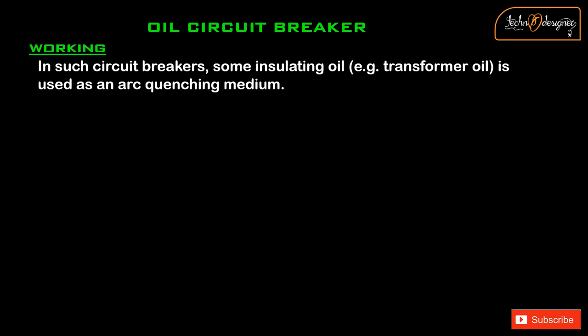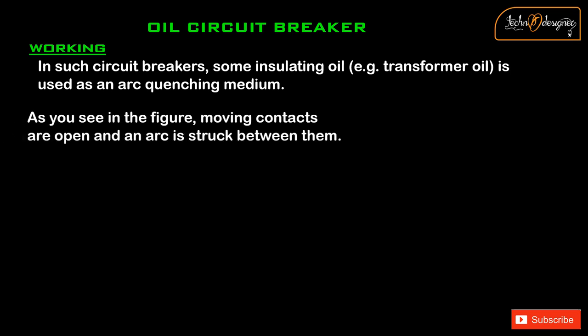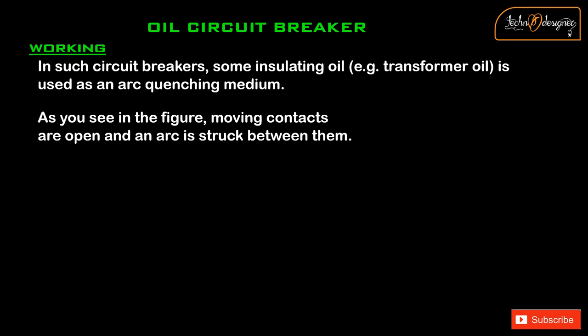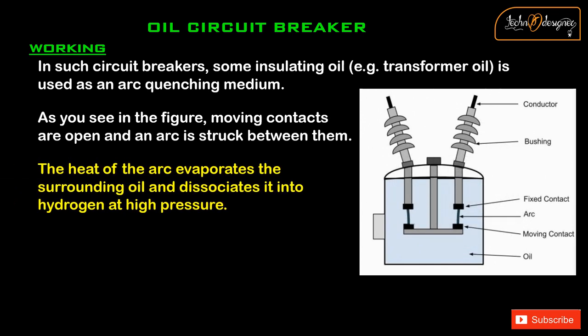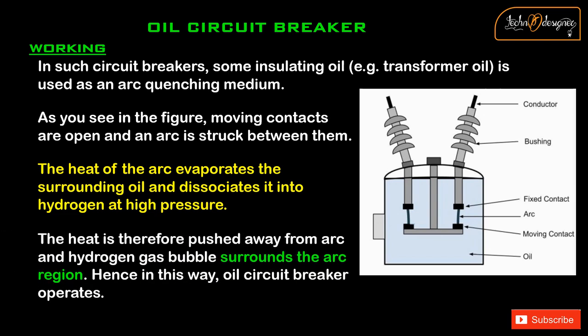Oil circuit breaker — Working: In such circuit breakers, some insulating oil, for example transformer oil, is used as an arc quenching medium. As seen in the figure, moving contacts are open and an arc is struck between them. The heat of the arc evaporates the surrounding oil and dissociates it into hydrogen at high pressure. The heat is therefore pushed away from the arc, and a hydrogen gas bubble surrounds the arc region, thus allowing the oil circuit breaker to operate.